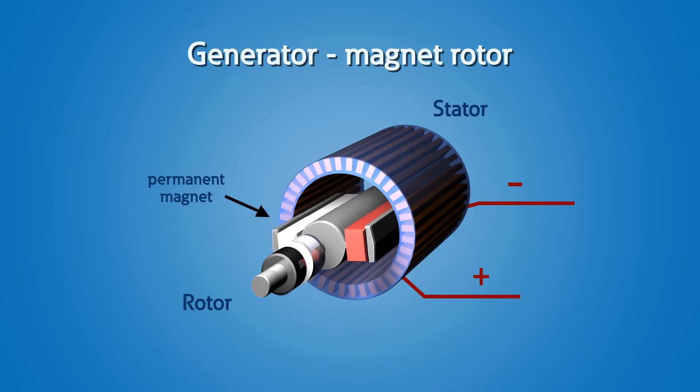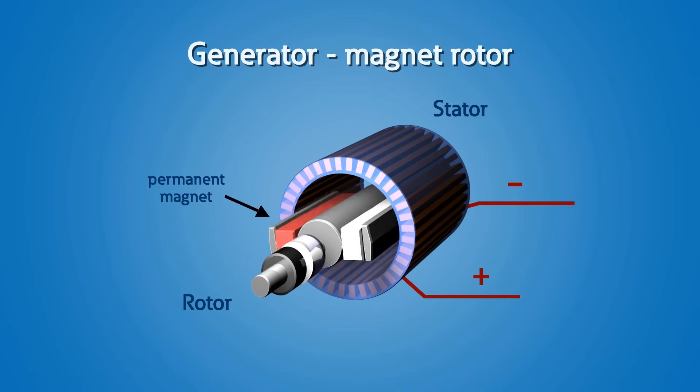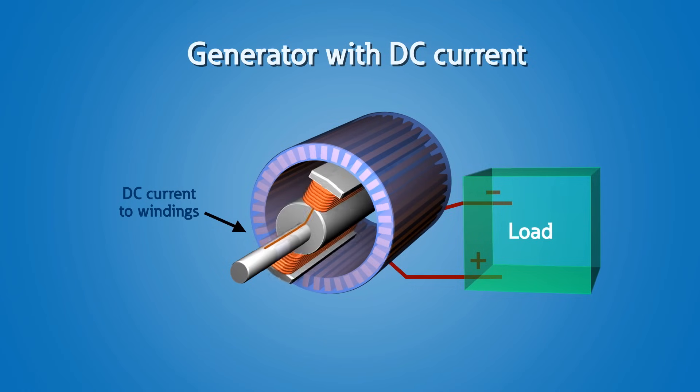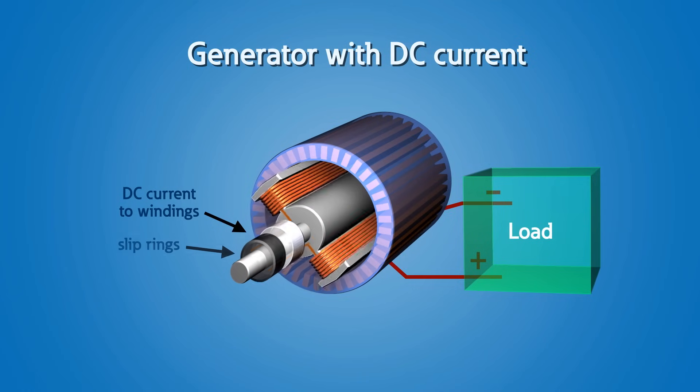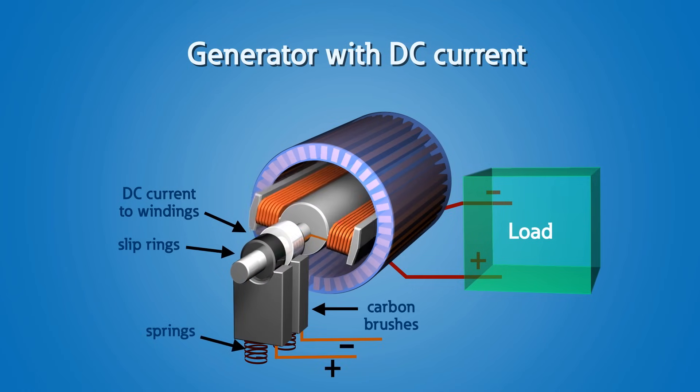The rotor spins inside the stator, and one full rotation is equal to a complete cycle of power. In North America, this equates to one 60 Hertz cycle. For a generator to produce power, electromagnetic induction must occur between the field windings in the rotor and the armature windings in the stator. A magnetic field must be created in the field windings on the rotor. Traditionally, this was done using permanent magnets, but with larger scale generation being needed, electromagnetic field coils were able to produce substantially more power.